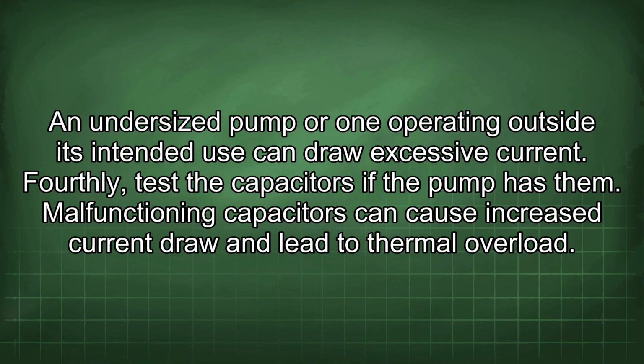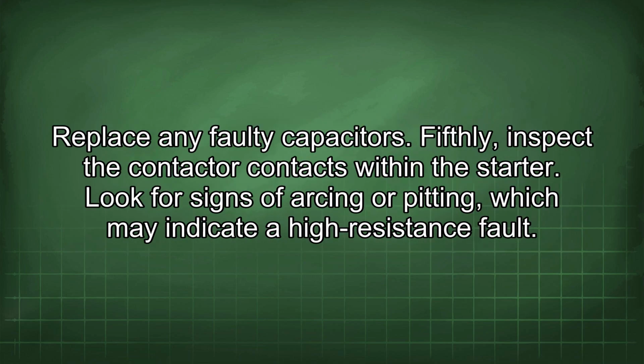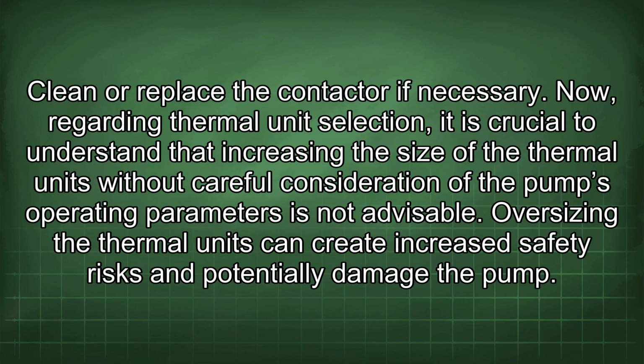Fourthly, test the capacitors if the pump has them. Malfunctioning capacitors can cause increased current draw and lead to thermal overload. Replace any faulty capacitors. Fifthly, inspect the contactor contacts within the starter. Look for signs of arcing or pitting, which may indicate a high resistance fault. Clean or replace the contactor if necessary.